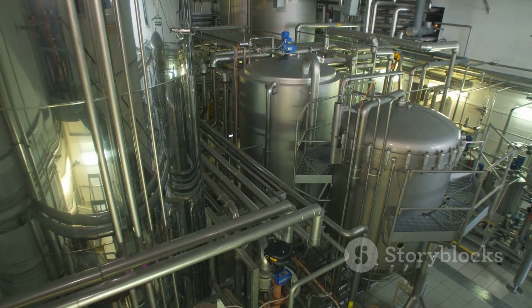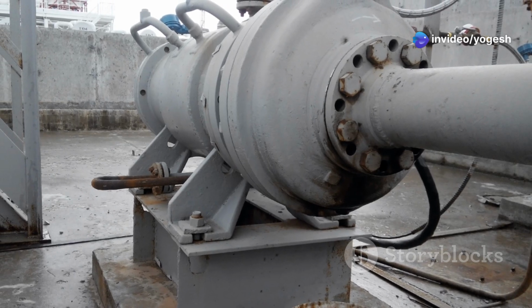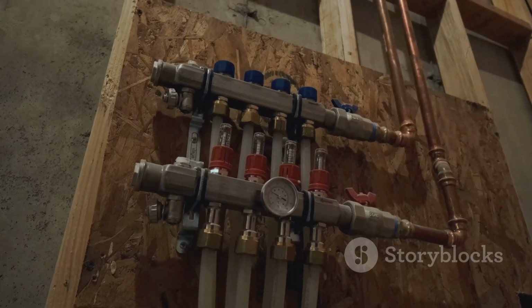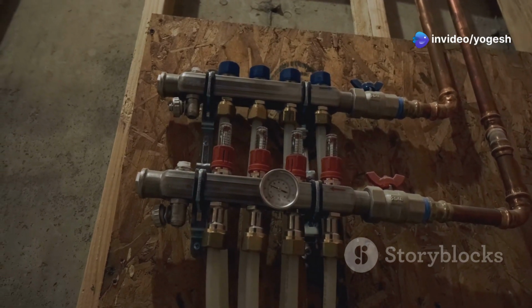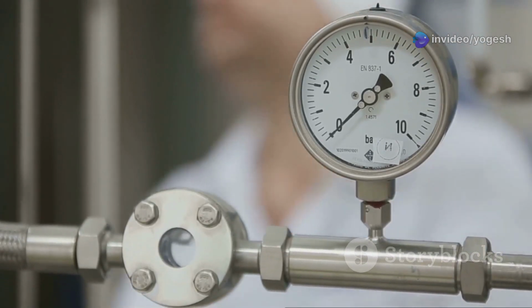Or consider how much chemical does a process require in an industrial setting. Head combines vertical lift, which is straightforward, and friction losses, which can be a bit more complex. These friction losses occur in pipes and fittings, and they depend on factors like pipe diameter, material, and the fluid's viscosity. Add up the vertical distance and friction losses carefully. Accurate calculations here are key.